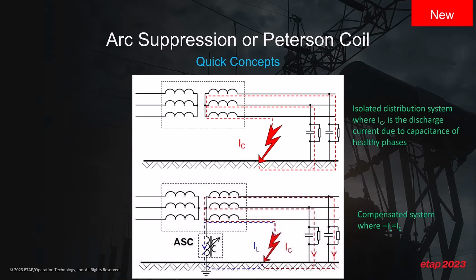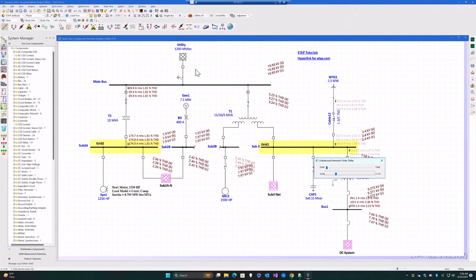So in ETAP 2023, you can simply model the arc suppression coil for the transformers, since it's part of the neutral, by adjusting the grounding type. So let's just see where this is available. Back to our ETAP software, we can select our one-line diagram. And in our one-line diagram, we can go to transformer T4, go to the grounding page and simply select Peterson coil. We can type in the resistance and the inductance value for the coil. And as soon as you click OK, we change, of course, the notation of the transformer grounding to show the inductance and the resistance in the star point or the neutral point of the transformer.